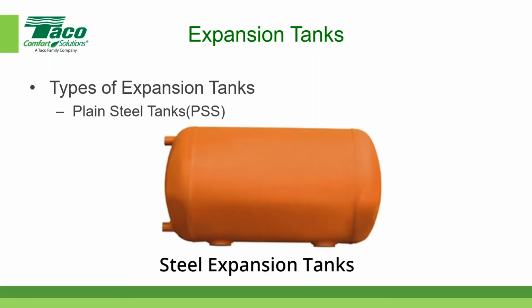Okay, now that we've gone through the narrative list, let's take a look at some photographs and see what they actually look like. So the first tank that we're going to talk about is called a plain steel tank. Now, a plain steel tank is just as the name implies. It's just a metal pressurized container. In this case, it happens to be mounted horizontally. On the left-hand side is a couple of connections, and typically what's connected to those two is a sight glass, and it allows the operator to determine the water level inside the tank. So if the sight glass shows the water level is here, then that would be the water level inside the steel container.